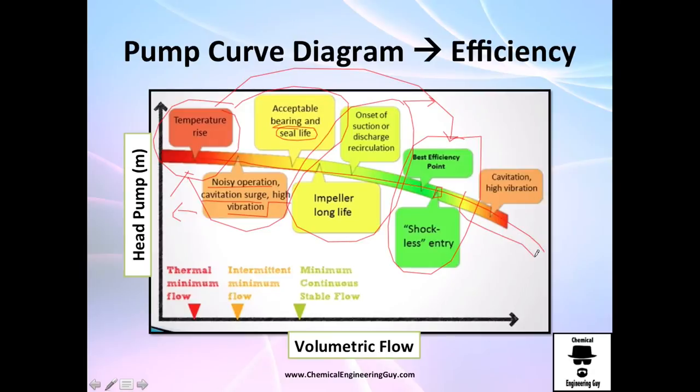And eventually if you just keep going to the right, you are going to see that once again we are going to achieve cavitation or even once again noisy operation, cavitation, high vibration and so on. So the best thing to do is to find the best efficiency point and stick to this.